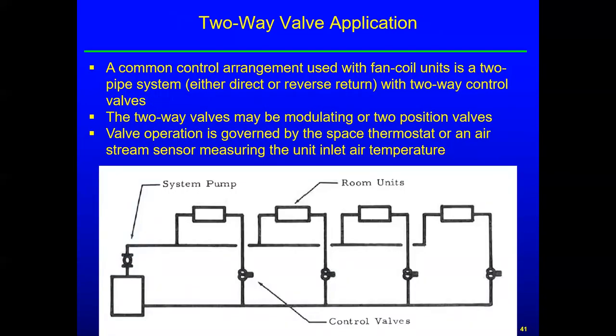Okay, so let's get on and look at a two-way valve application. So a two-way valve means that all this valve can do is close off against the flow. If it's strong enough and can resist the pump head, it can close completely off and kill the flow in that particular line. So these can be either modulating, which means they can respond to a thermostat and just modulate smoothly from complete open to complete closed and back and forth based on the set point and the desired temperature in the space. Or they can be two position valves, which either snap open and you get full flow, or they snap shut and you get no flow.